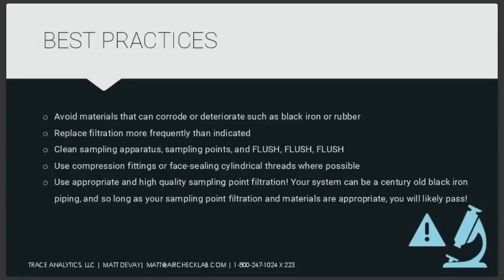And then use appropriate and high-quality sampling point filtration. I mean, you saw it over and over again in the slides. Old or ineffective filtration is always going to be the number one thing that will give you problems. Your system can be century-old black iron piping, all types of polymer tubing everywhere, and so long as your sampling point filtration and materials are appropriate, you're pretty likely to pass your testing.